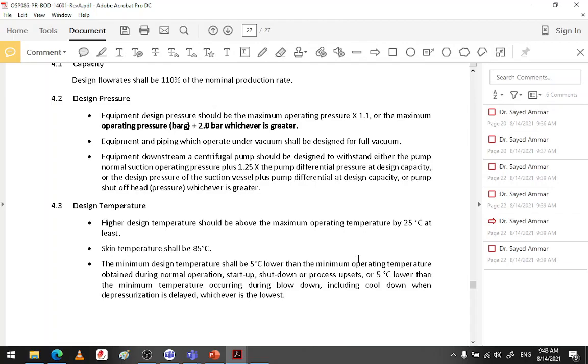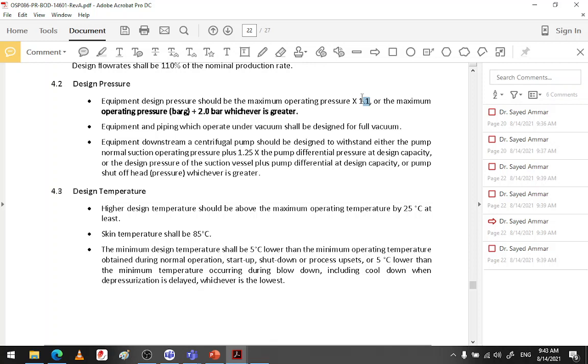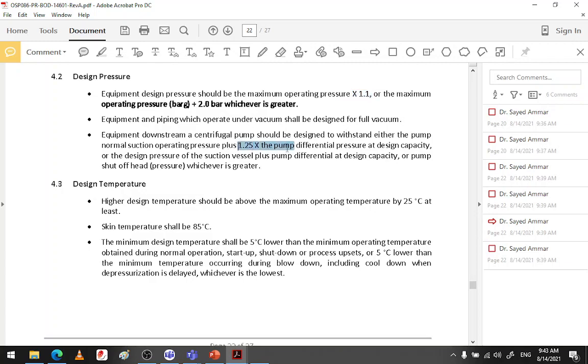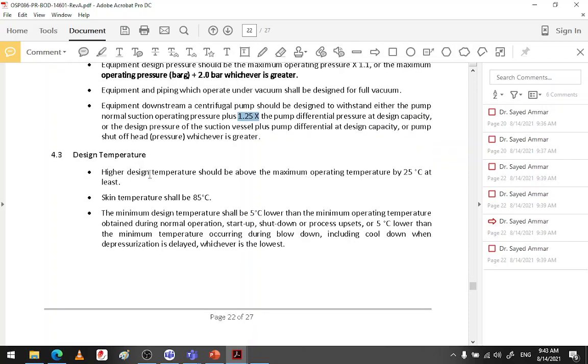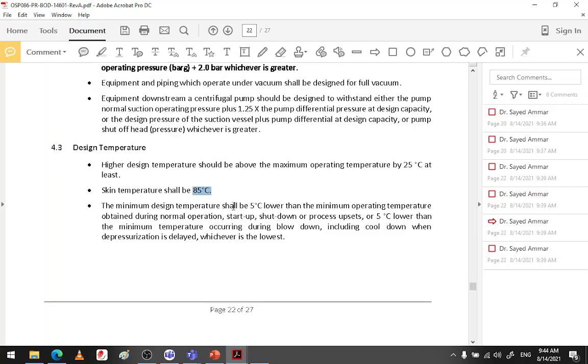Design pressure, design temperature. He, as a client or as an EPC contractor, considers 1.1 and 1.25 for the pumps, 1.1 for the static equipment, 1.25 for the rotating equipment. For the design temperature, he considers the skin temperature to be 85, and the minimum design temperature shall be 5 Celsius lower than the minimum operating temperature obtained during normal operation, startup, shutdown, or process upset, or 5 lower than the temperature occurring during cool down, including cool down when depressurizing is delayed, whichever is the lowest.